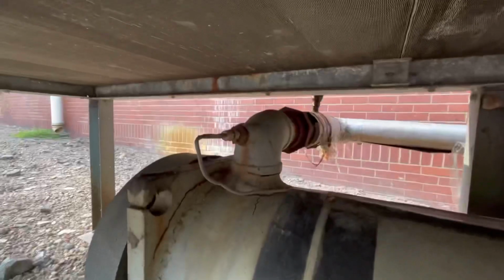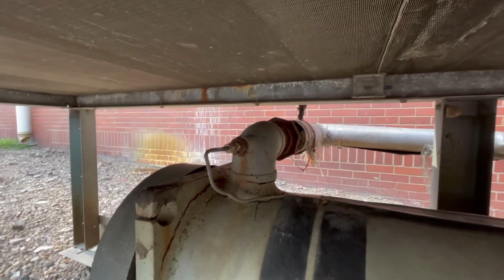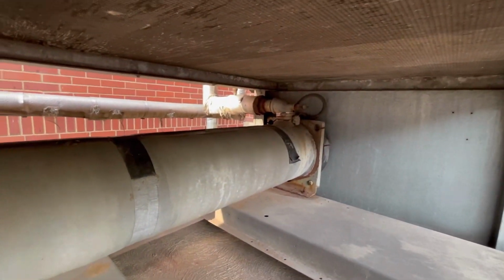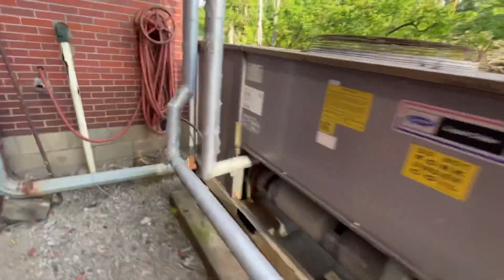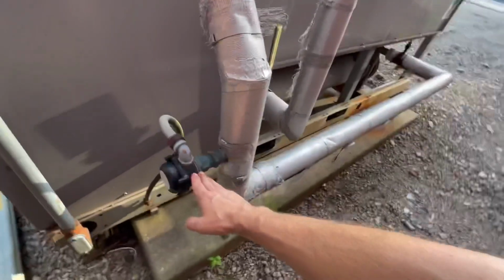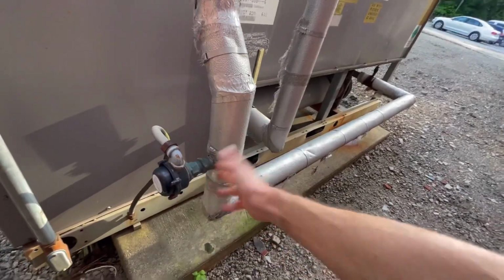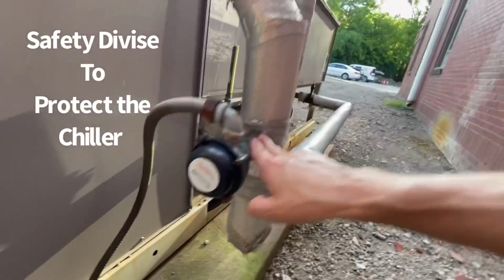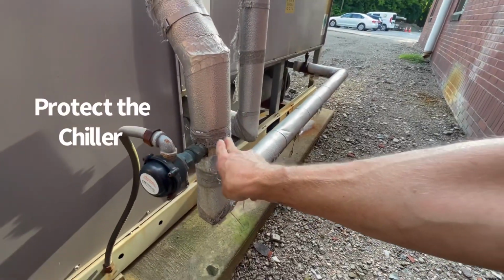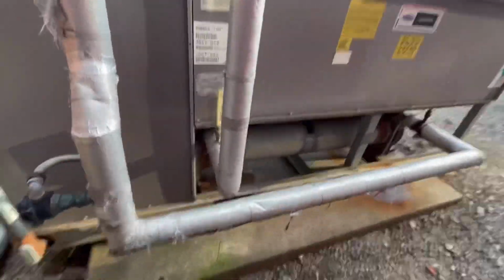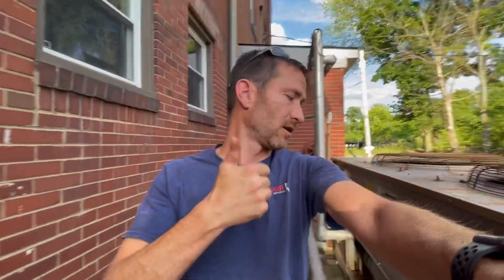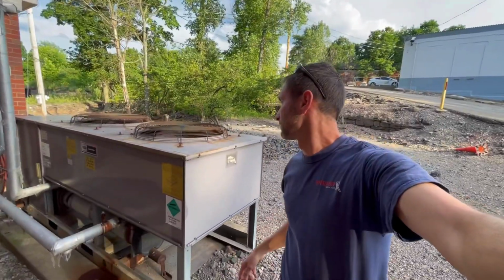Inside of here they have a sensor that detects the water temperature, that tells your chiller whether we need to cool this down or not. Also there is a flow switch - if our circulator pump shuts down we'll have no flow. There's a paddle type in here, this is McDonnell Miller, it'll have a paddle inside sensing flow, whether your circulator is running or not. That's one of the worst things you could do for a chiller, basically running it dry with no flow. Okay, let me see, that's dripping away.